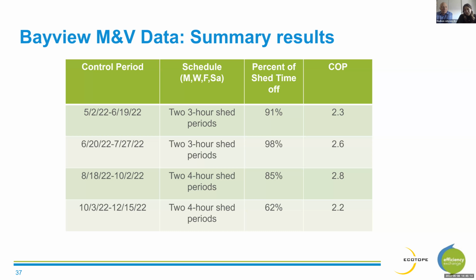We were even more successful in the second control period, which was from June through July. It was again 2 3-hour shed periods, and we kept the system off for 98% of the scheduled time. And that 2% is usually just due to a little bit of a lag in the system, like maybe it turned off a minute after it was supposed to. So this was really successful.